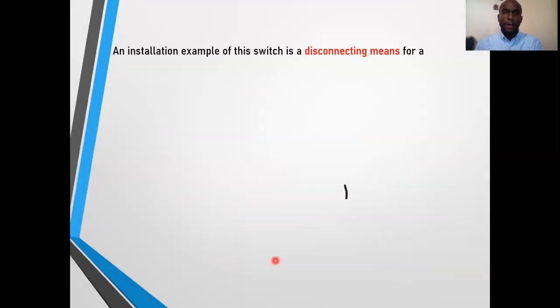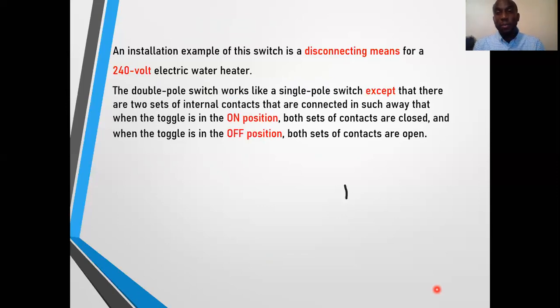Let's look at some important facts about the double-pole switch, for example, how is it used. It is used as a disconnecting means for a 240-volt electric water heater. Now, the electric water heater can range in current values from 20 amperes to even 30, even 50 amperes, depending on its application and its size. So if you want to have a disconnecting means by which you are able to control this water heater from the location of the water heater and don't have to worry about going to a breaker panel to disconnect it, you can use a double-pole switch.